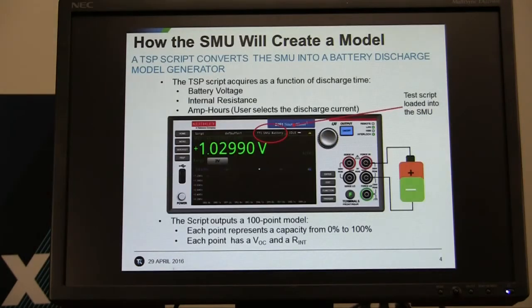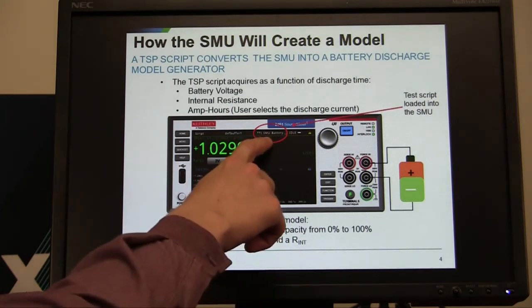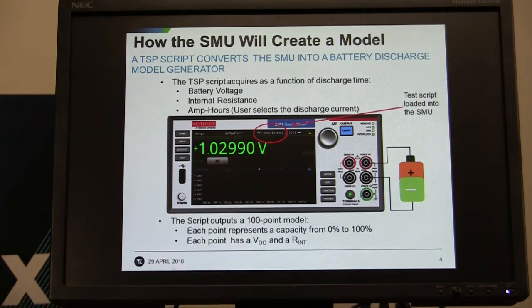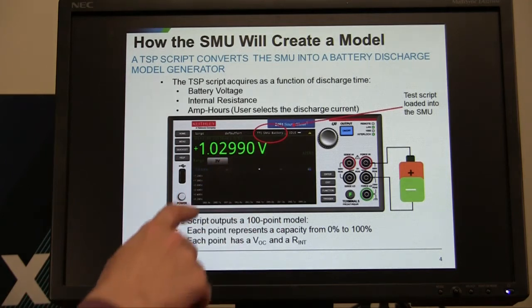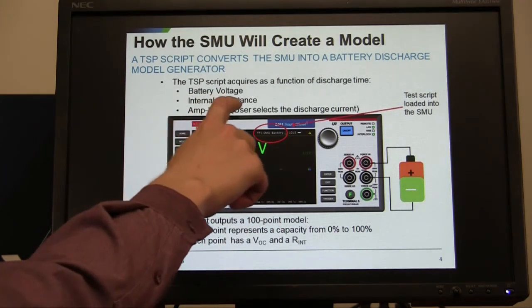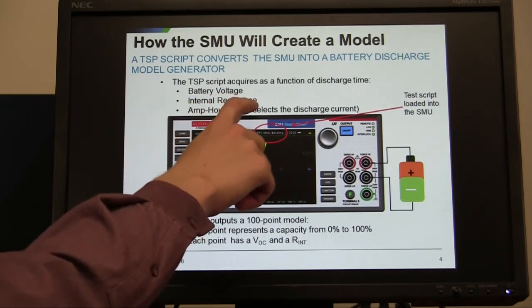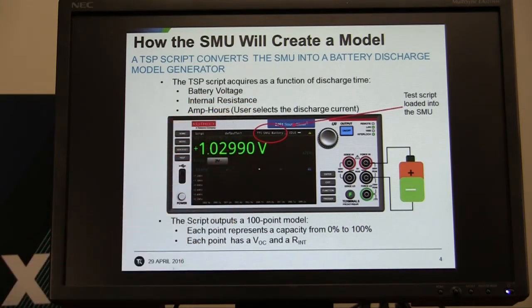So how is the SMU going to create this model? Essentially you're going to load a TSP script from the front panel and that TSP script will run and collect battery voltage, open circuit voltage, internal resistance, and amp hour capacity data from the battery.